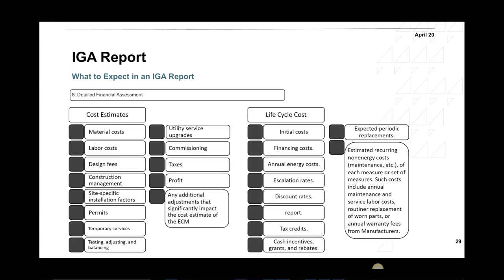Detailed financial assessment, cost estimates. What needs to be there as cost estimates for the capital cost? This is mainly coming from ASHRAE 211. So the material costs, labor cost, design fees, construction management, site-specific installation factors. Let's say you're working on a building that has restricted access for only a few hours a day, and then your cost would go higher. Permits, temporary services, TAB (testing, adjusting, and balancing), utility service upgrades, commissioning, taxes, profit. All these things need to be shown separately, which is rarely shown in the energy audits that I've seen here. But this is the 211 requirement. You need to show a breakdown of costs.